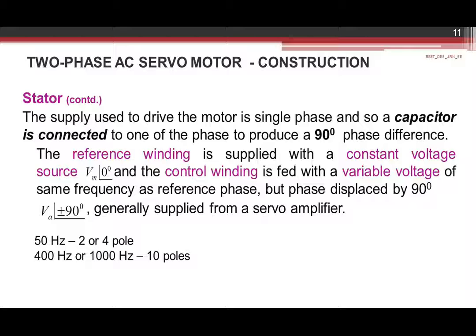The stator has to be fed with a voltage with a phase displacement of 90 degrees. The supply used to drive the motor is single phase, so in order to have 90-degree phase displacement, a capacitor can be connected to one of the phases — generally to the reference winding. The reference winding is supplied with a constant voltage source, represented as Vm∠0°, and the control winding is supplied with a variable voltage of the same frequency but with a phase displacement of 90 degrees: Va∠+90° or Va∠−90°. This is generally supplied by a servo amplifier. For 50 Hz applications, 2-pole or 4-pole motors are used, and for above 400 Hz, 10-pole motors are used.